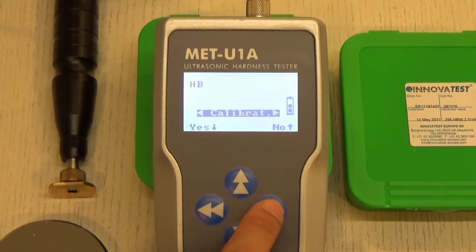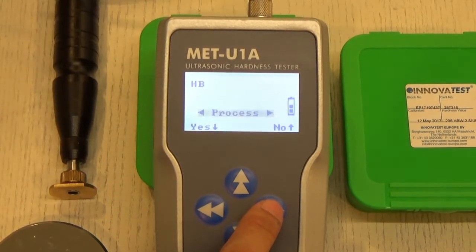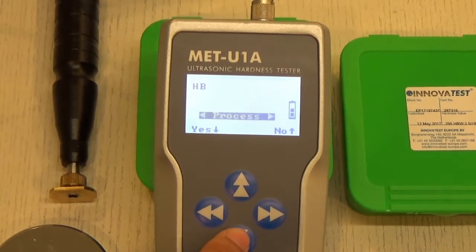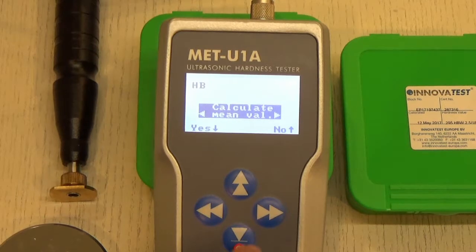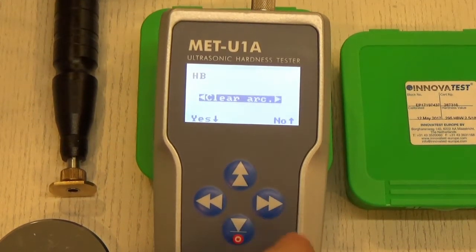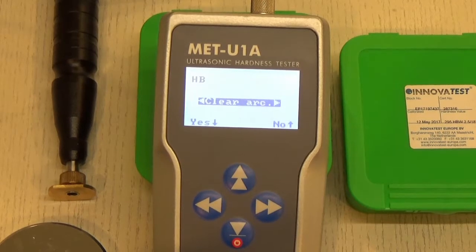From the settings page, pressing right takes you to the calibration mode, and further right takes you to the process. Press the down button to enter a setting. In the process setting, one option is to calculate the mean value for all readings, and the second is to clear all archived readings stored in the tester.